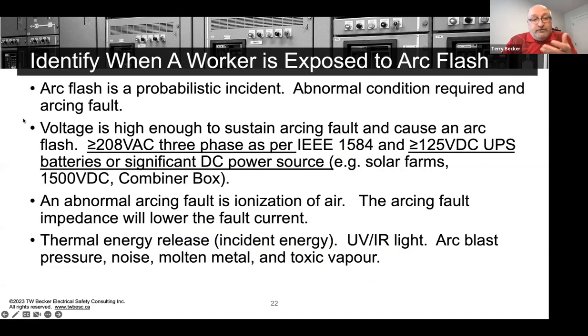So an abnormal arcing fault is a probabilistic event, right? And these are the volts of concern, 208-volt three-phase from IEEE 1584. That's still the, quote, current documented research from a credible organization. And then for DC, they haven't formally studied that under IEEE 1584 yet, but other organizations have. And the one that I quote the most is the DOE in the US in their labs. And I'd say in the last 5 to 10 years, they've started to share generic information that they can about electrical hazard classification. And for DC, it's nominal 125 volt DC UPS battery output or other significant DC power source.